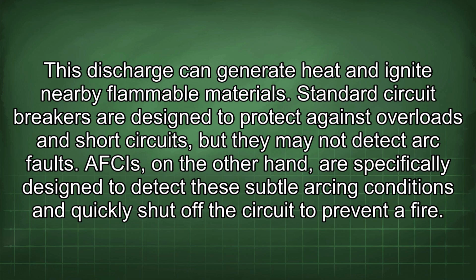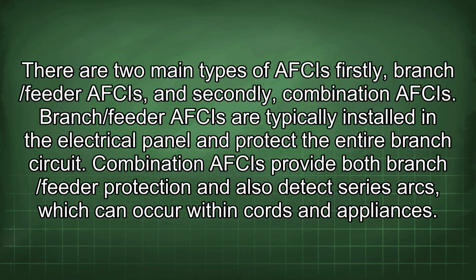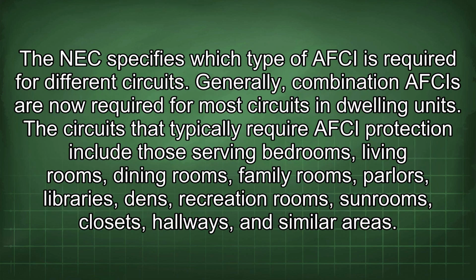to prevent a fire. There are two main types of AFCIs: firstly, branch/feeder AFCIs, and secondly, combination AFCIs. Branch/feeder AFCIs are typically installed in the electrical panel and protect the entire branch circuit. Combination AFCIs provide both branch/feeder protection and also detect series arcs, which can occur within cords and appliances. The NEC specifies which type of AFCI is required for different circuits. Generally, combination AFCIs are now required for most circuits in dwelling units.